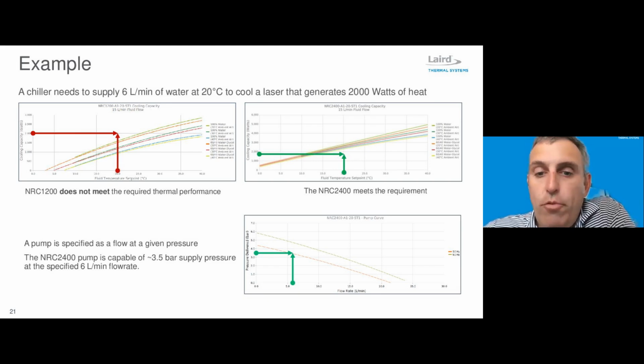If we go to the performance curve of the pump for the NRC 2400, you can see that at 6 liters per minute, the system is capable of delivering about 3.5 bar of pressure. That's a little bit over 50 psi, and that's at 50 hertz. If we look at the 60 hertz curve, the green one, which is the higher of the two, you can see the performance is increased due to the higher motor speed.